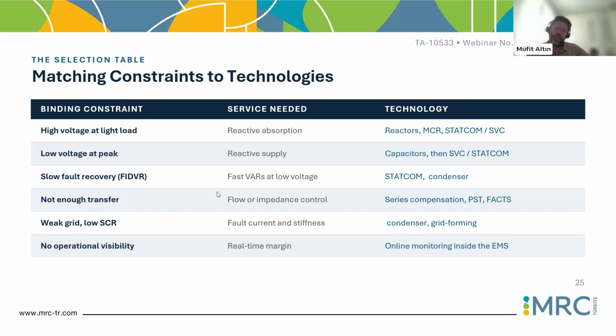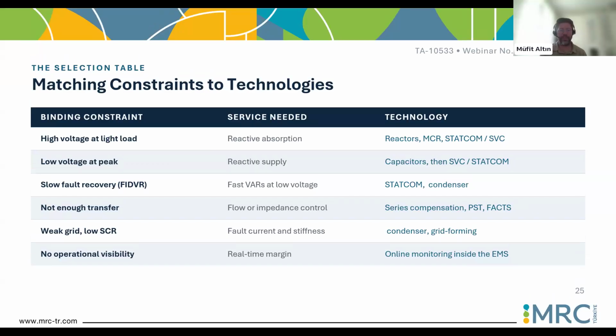Of course, when you switch to the new technologies, STATCOMs and SVCs are always there, even for steady state or static requirements. You can use STATCOMs, SVCs. They are, of course, just for this purpose, but expensive. And when we switch to another constraint, low voltage at peak, then you need, as the reverse of the absorption, to supply reactive power with capacitors, similar to the reactors. You can install your capacitors fixed, and you don't need to control them; they can be there, and you can supply your reactive power. Of course, you need to control the voltage variations around the local area, because they are dependent on the voltage values. And again, as an absolute solution, you can use SVCs and STATCOMs, expensive ones, but you can use them.